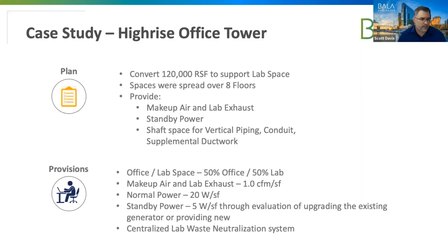As mentioned, when I went through the metrics, we have makeup air, we have lab exhaust that we provided in a core shell environment, a certain amount of standby power available, and then we did create new shaft space. We were not able to use existing shaft space, or as Chuck noted in the last case study, we were not able to utilize an elevator. In some cases, there might be extra elevator space, so the team is able to determine that one of them can be removed and put into use as a shaft. We just didn't have that luxury on this project.